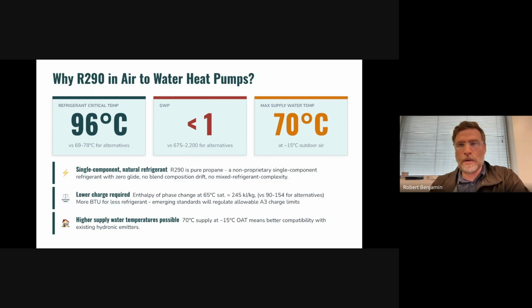So why R290 then, specifically in air to water heat pumps? We'll talk about comparisons against other refrigerants, but there are a lot of reasons why, as someone putting these systems into buildings and homes, we'd like to use this refrigerant in our heat pumps. Currently we use R32, which is a very decent refrigerant, and I believe it really is the right choice for some things.